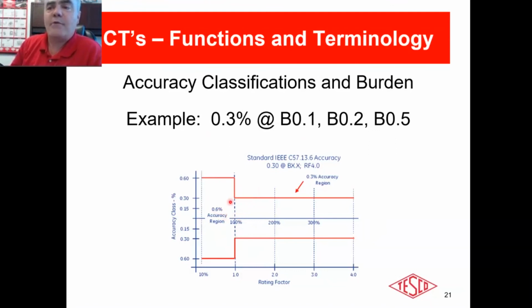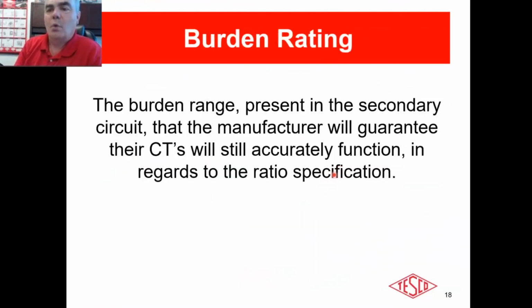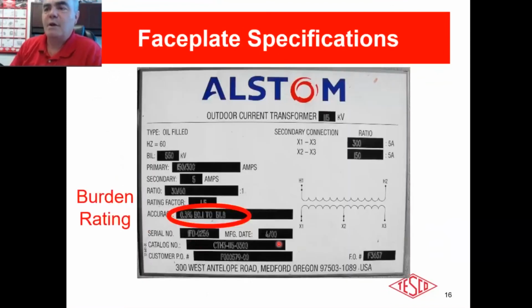Now, I'm going to go back up to my faceplate here. Where on this faceplate does it say that it is 0.6% accurate if you're at anything less than, say, 300 amps if I've hooked up the X1 and X3? So take a quick look at that if you can see it on your screen. And the answer is nowhere on this faceplate does it tell you that it goes to half the accuracy. That is just something that we are supposed to know.